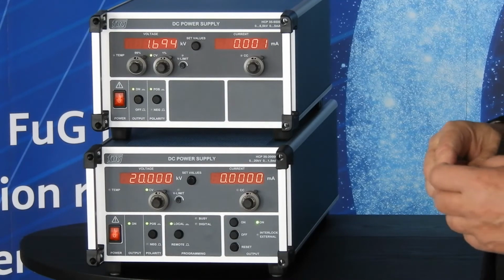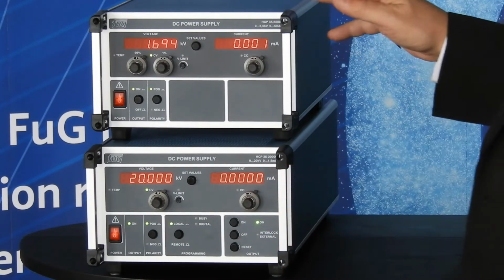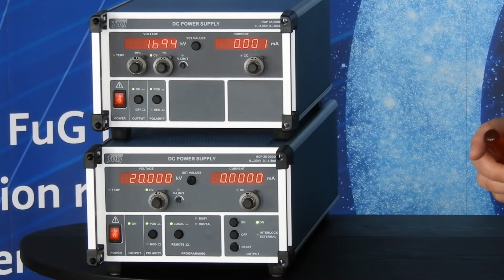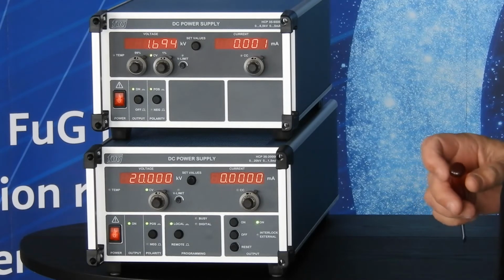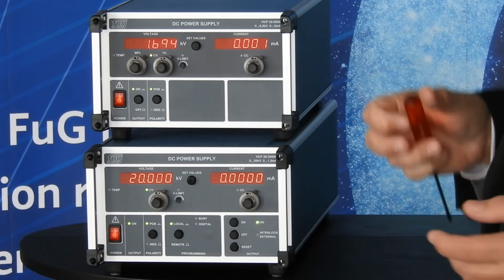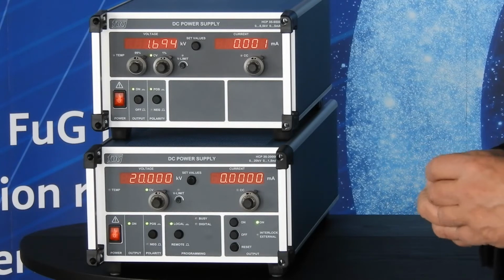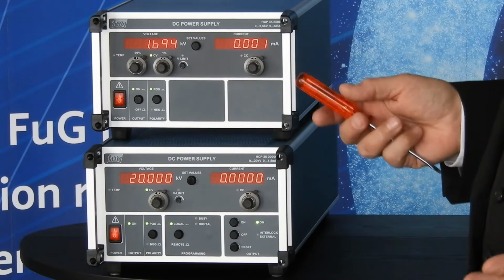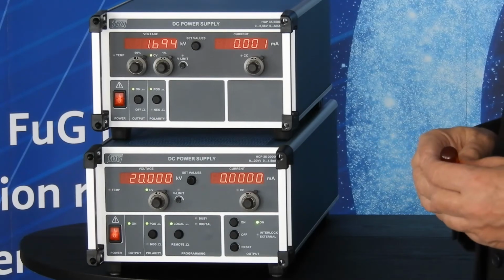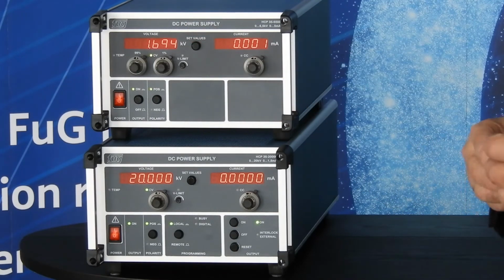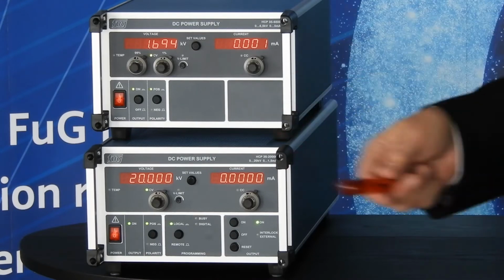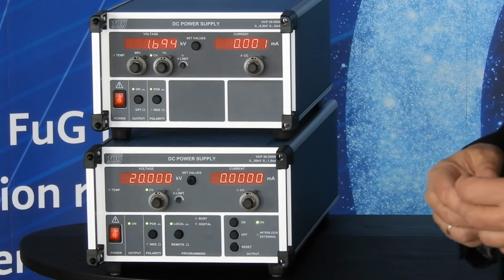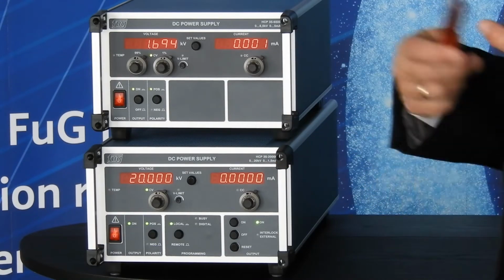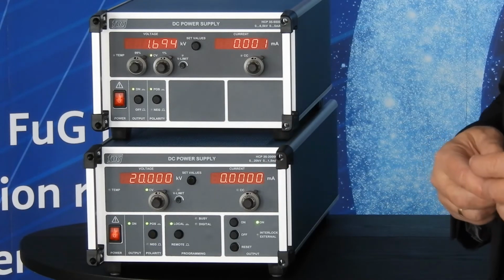The polarity switch which we use for these small power supplies is not for very frequent use. You should not use it more than, say, 100 times a day. It is designed for use 1, 3, or 10 times a day. This polarity switch can operate approximately 10,000 moves over the lifetime of the power supply. So if you have an application where you need to change polarity every minute or every 10 minutes, please tell us and we will find a special solution for you.